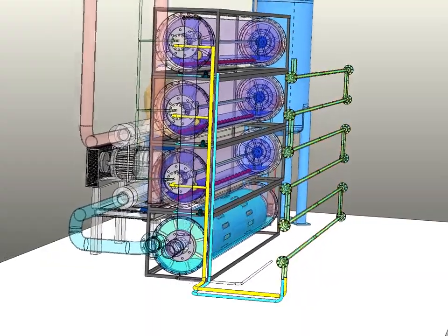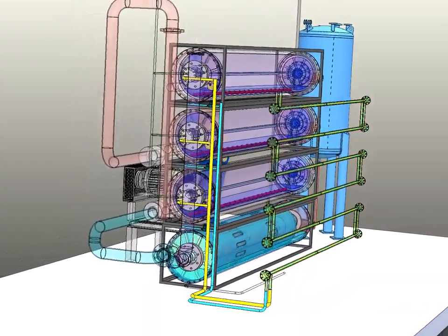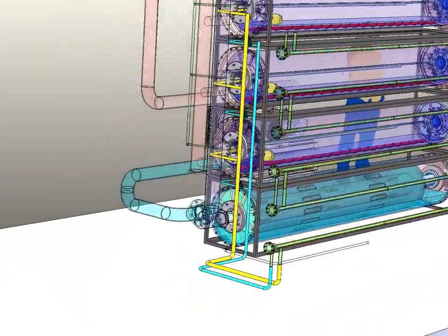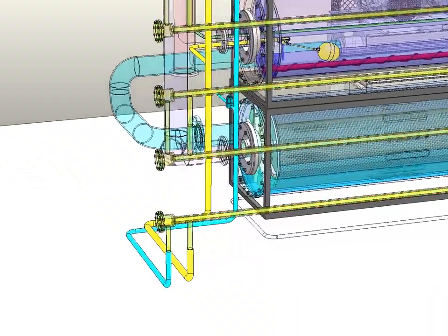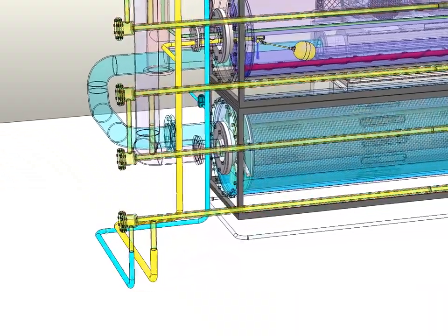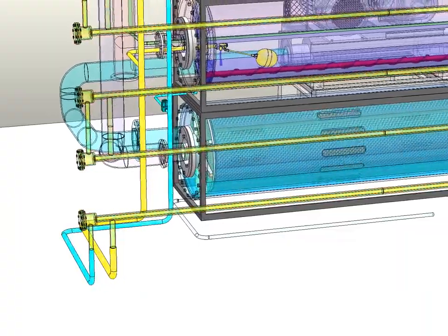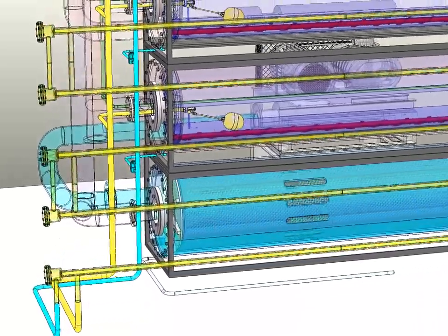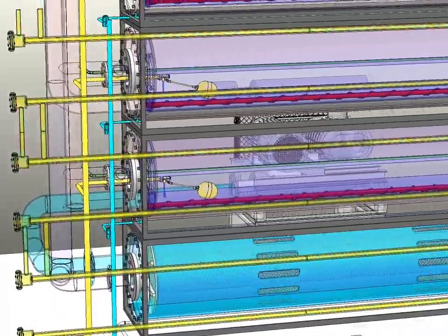When evaporating solutions with surfactants, foam may form. When the foam bubbles are destroyed, aerosols are formed that pollute the secondary steam. The module of a horizontal packed mass exchange apparatus located in the lower part cleans the contaminated steam from aerosols. The solution level in the drums is automatically adjusted using float valves.